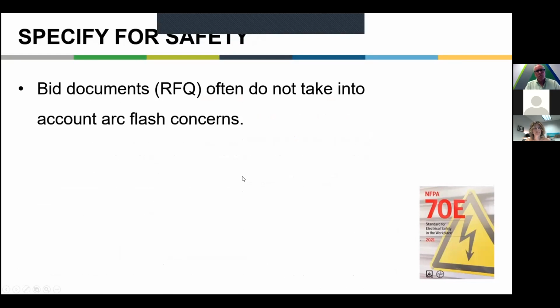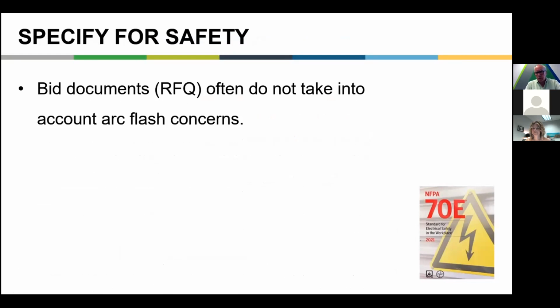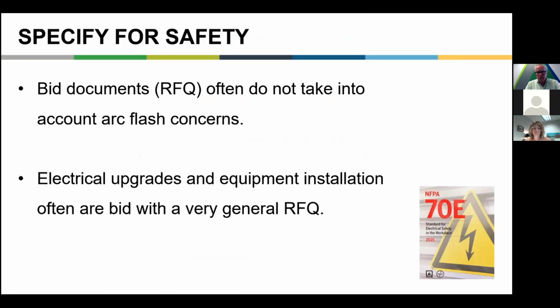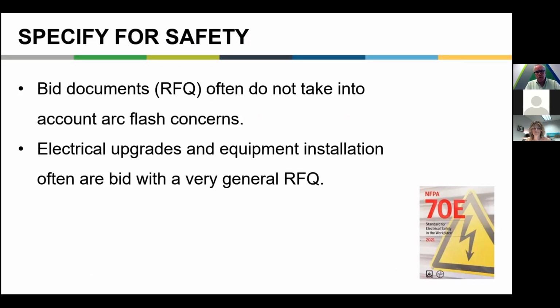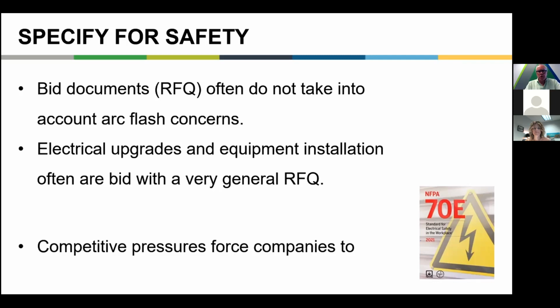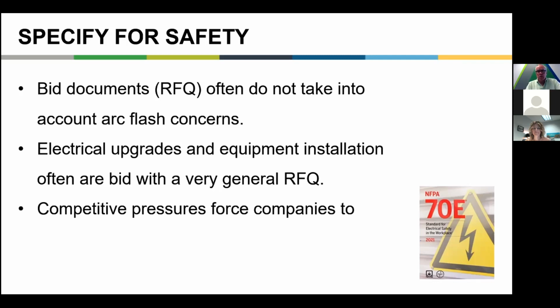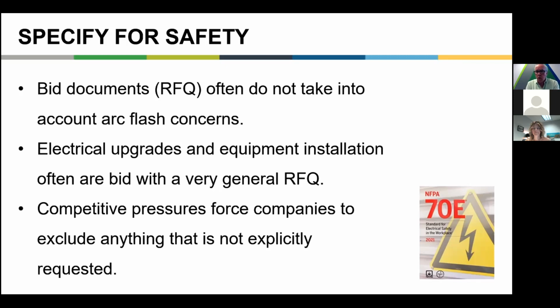Okay, so specify for safety. Bid documents, requests for quotations, often do not take into account arc flash concerns. The vast majority. Electrical upgrades and equipment installation often are bid with a very general request for quotation. Competitive pressure forces companies to exclude anything that is not explicitly requested. So bottom line, if you don't ask for something to be included in a contract, it will not be.